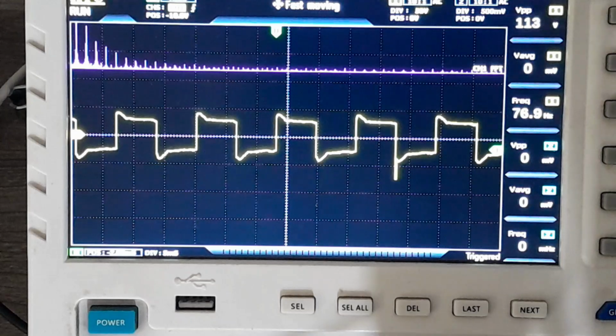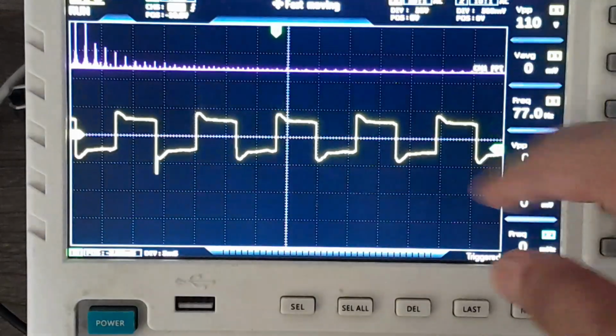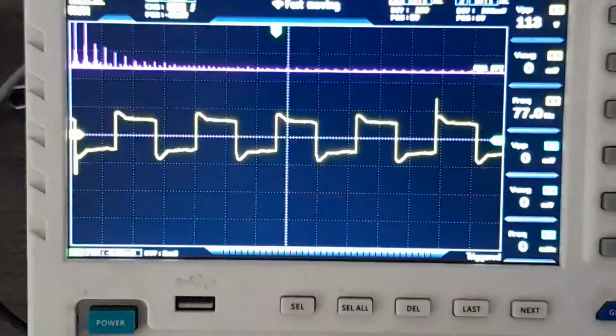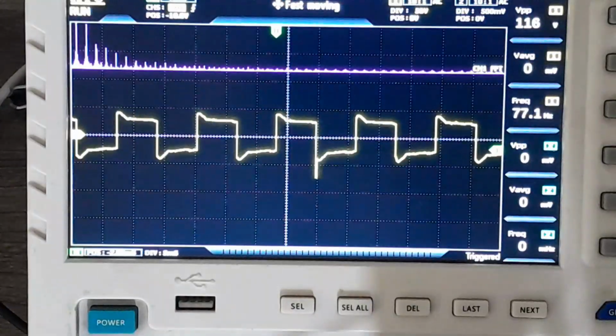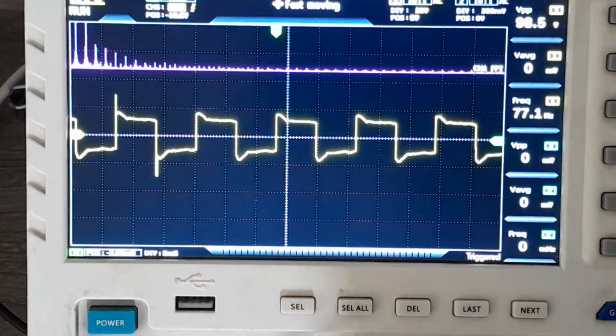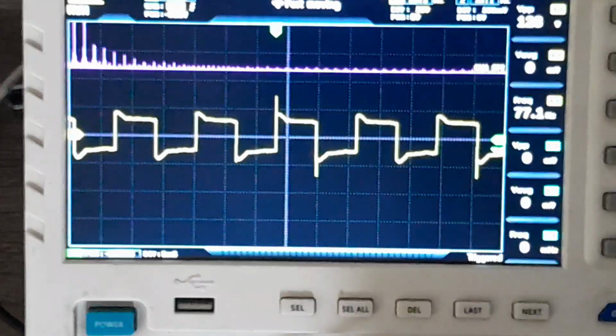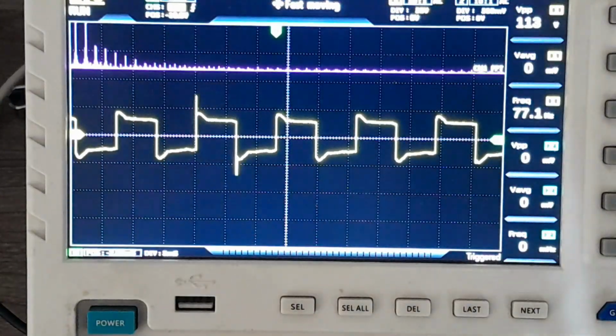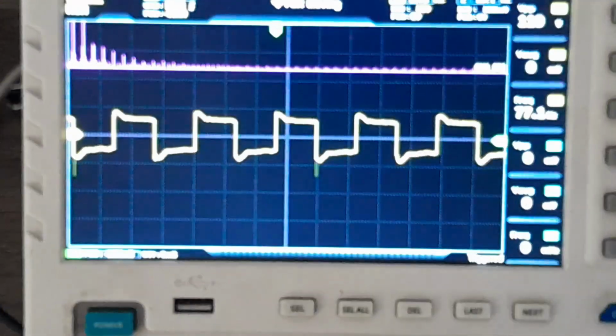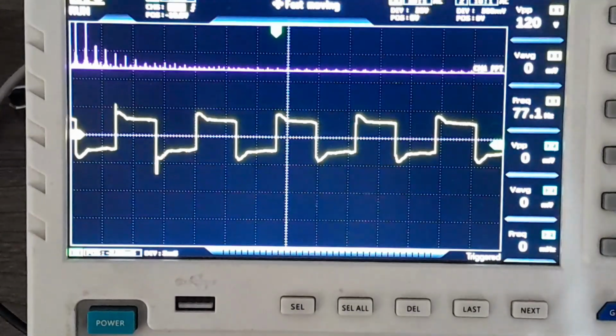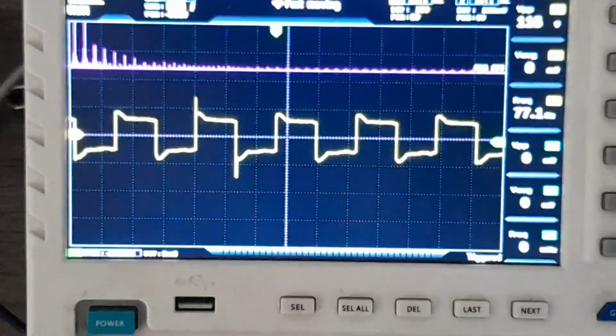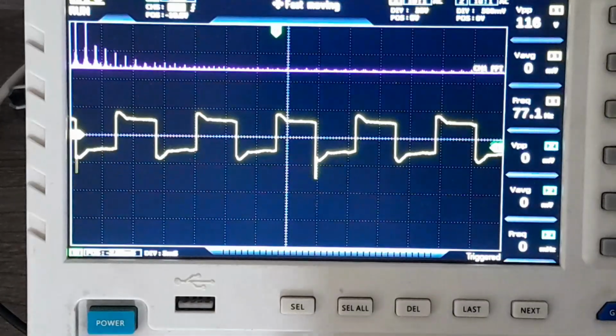At 76 Hertz, there's torque, and you can see as the frequency decreases the voltage should decrease. So I decreased the voltage, otherwise the motor will burn, because at different frequencies the motor will react differently, since the motor behaves like an inductor, and inductors behave differently at high and low frequencies.